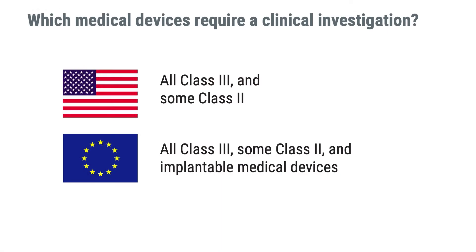In the United States, all high-risk medical devices — such as class 3 devices and some class 2 — require a clinical investigation. In the EU, all high-risk devices such as class 3 devices and implantable medical devices require a clinical investigation, and some class 2 devices require one too. There may be some exceptions to this, and you can learn more about how to classify the risk of a medical device in our course on CE marking of medical devices.